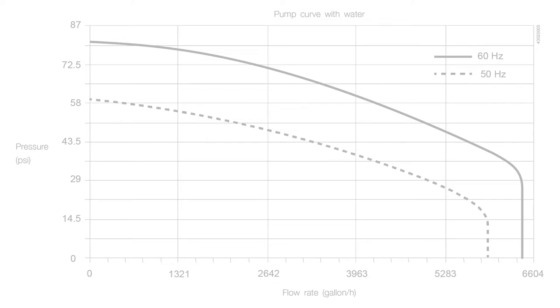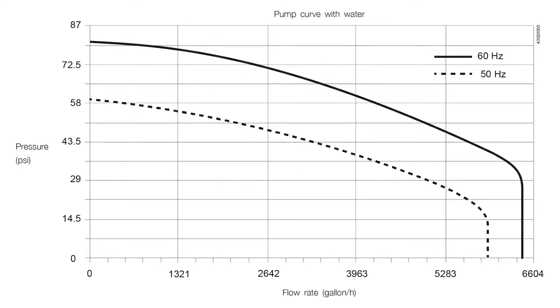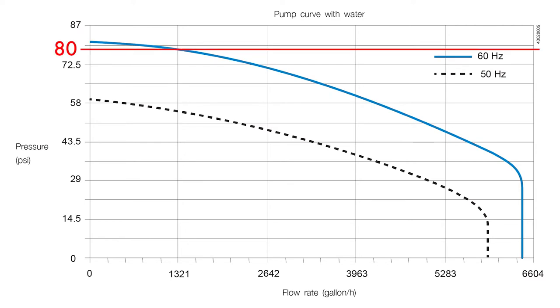Now let's put head and flow together. Let's say you want to know the flow rate to expect from a pump at 60 hertz when the pressure is 80 psi. In this example, the flow rate is 1,321 gallons per hour.